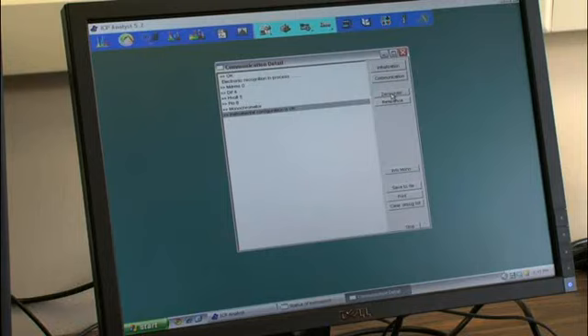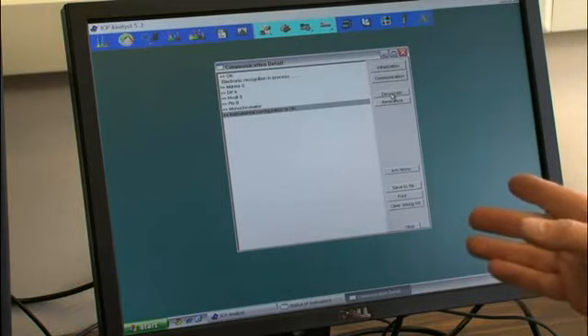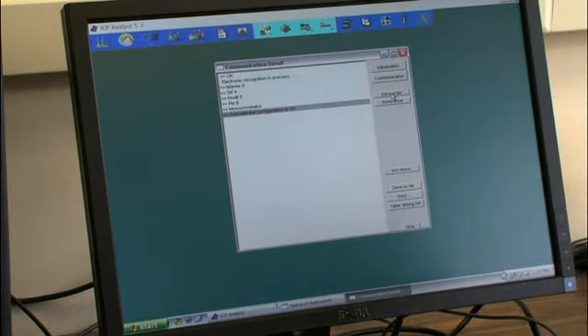The reference wavelength that we're using is a carbon line, and the reference wavelength has to be something that's always in the plasma, either argon, or nitrogen if you're purging with nitrogen all the time, or carbon. And I don't know why carbon is there. It's not combusting, so it's just there. Maybe from the water. So it's going to do 4 scans.